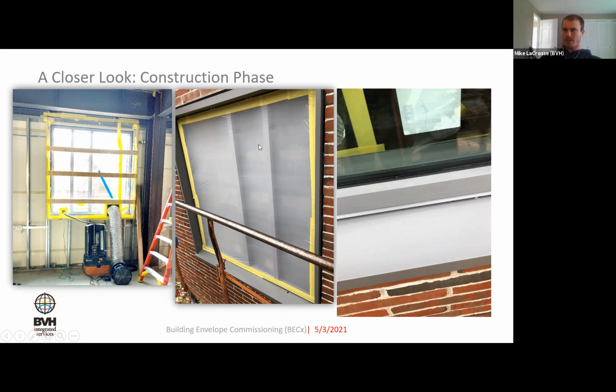But one thing that was really concerning is when we depressurized our unit from the inside and put this plastic up on the outside, look at what this plastic's doing. It's getting pulled right in against the outside of the window itself. So that might tell us we're actually pulling air through the unit, from the outside all the way to the inside.